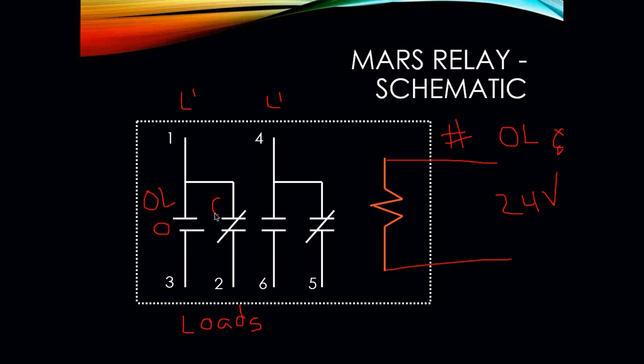If I'm going across 1 and 2, I should be reading 0. Why? Because that's a normally closed switch. A switch is a power passing device. It has no resistance. I should be reading 0. If I read OL here, that's telling me that my switch, my normally closed switch, is open. And the relay needs to be replaced. There's nothing we can do to repair it out in the field. We take the relay out, we put a new one in, and wire it. And that is your sequence of operation and how a relay works.